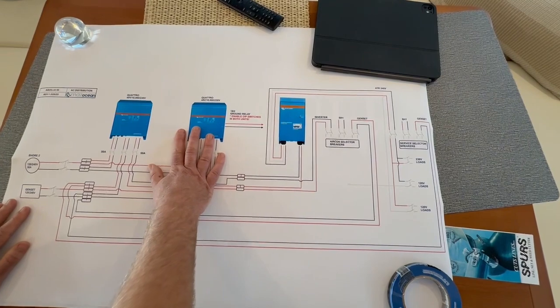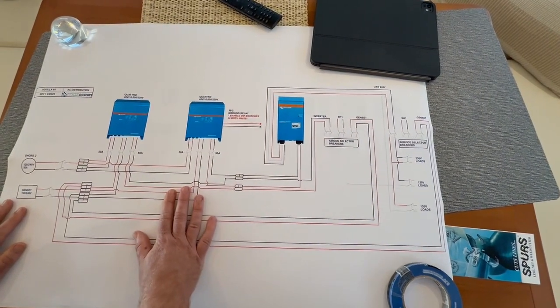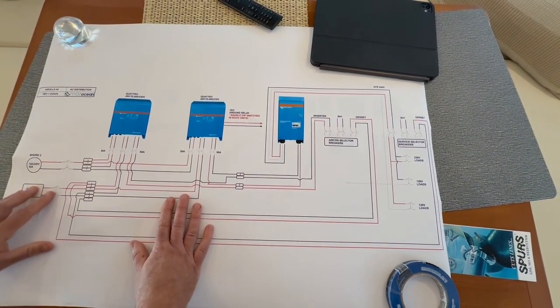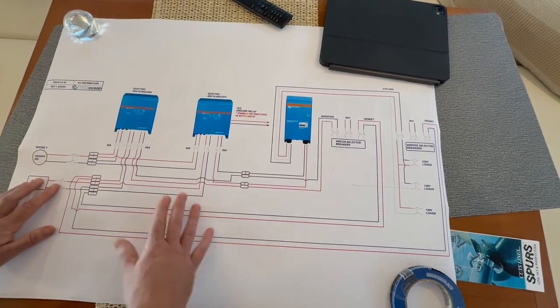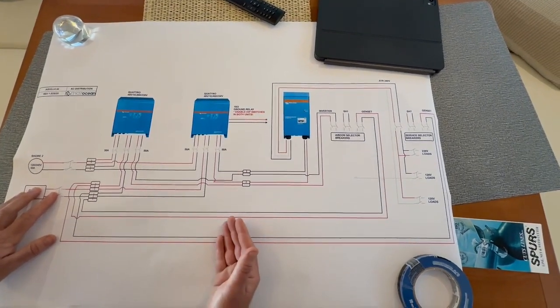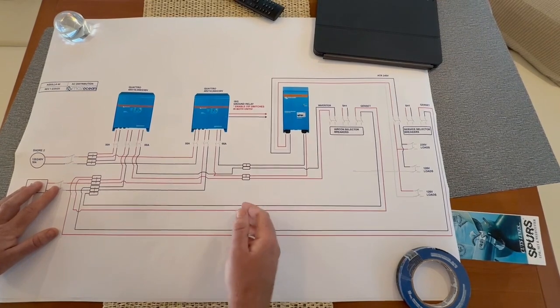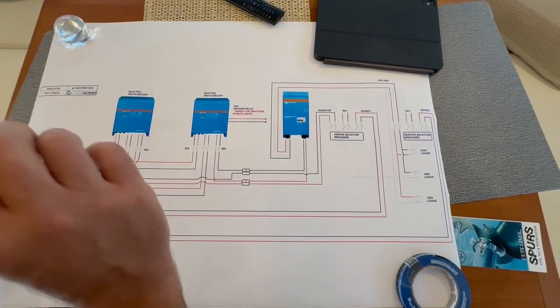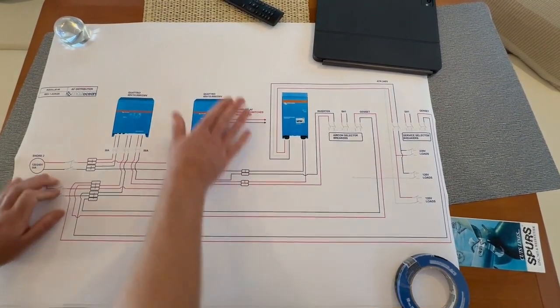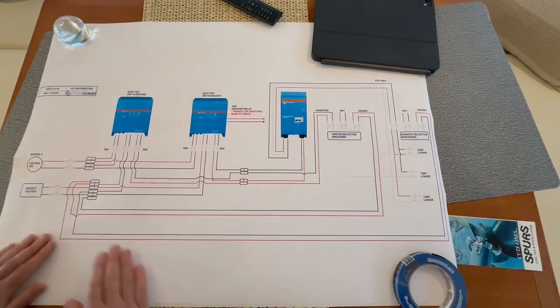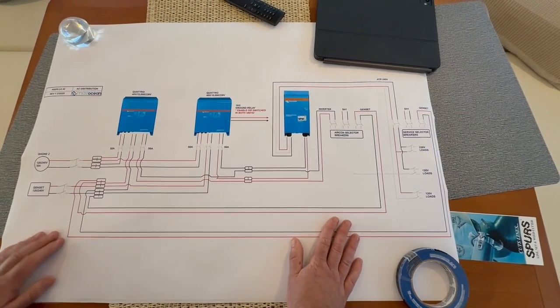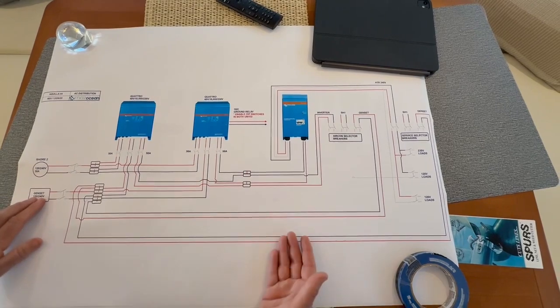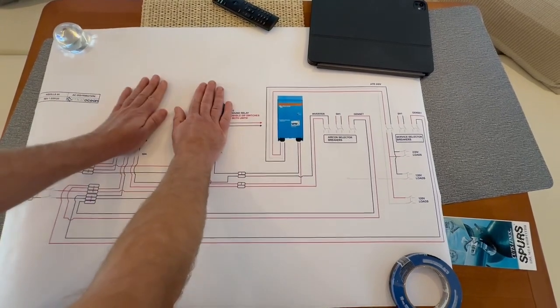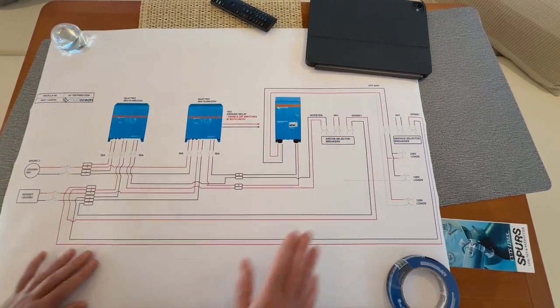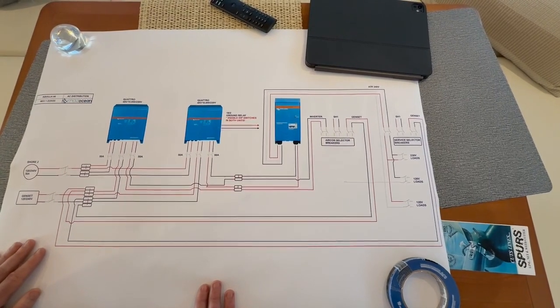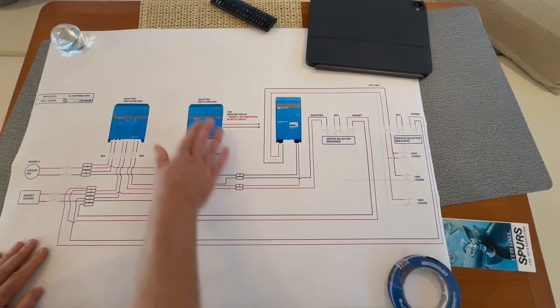So we created two bypass options. One, this vessel originally had two shore power inlets, and one of those is now a bypass option. There are selector switches on the main distribution panel that just need to be reoriented to allow shore power to bypass the two Quattros and feed everything directly. Our second bypass is if you're not on shore power, the generator can also bypass the Quattros and feed the vessel directly. So we've given Curtis two great bypass options if he were to have a failure.